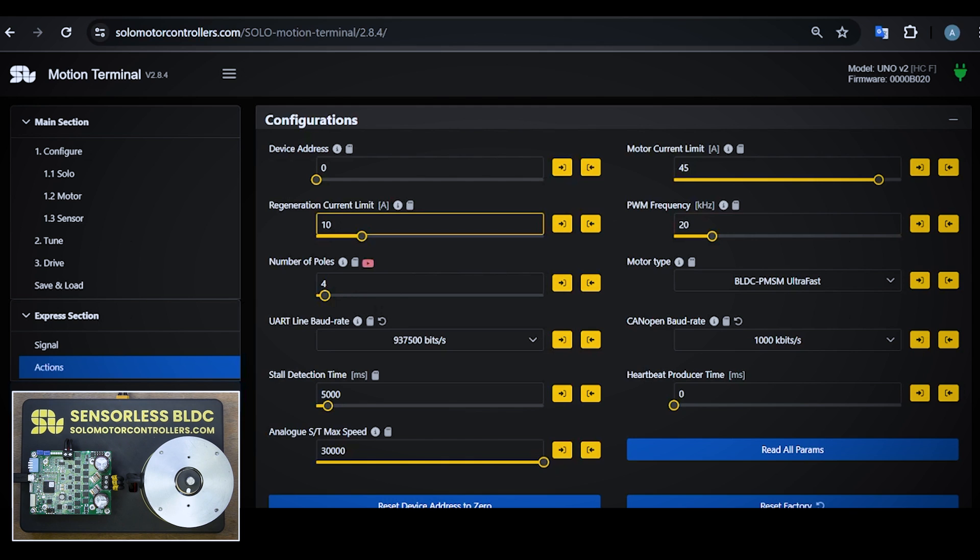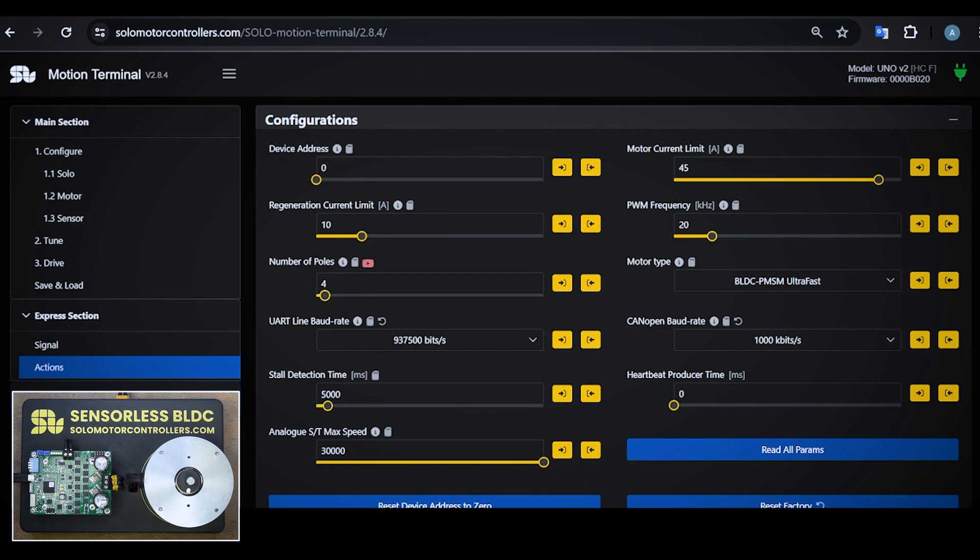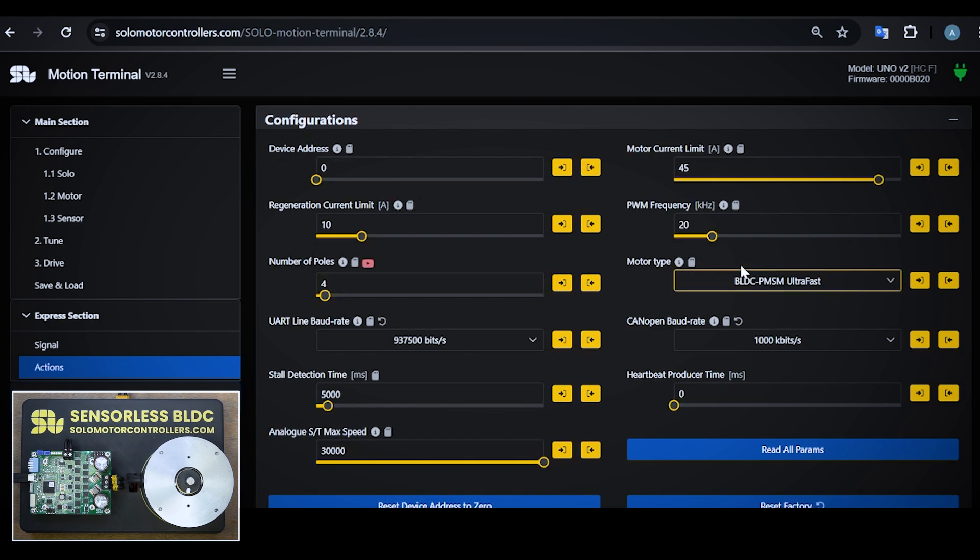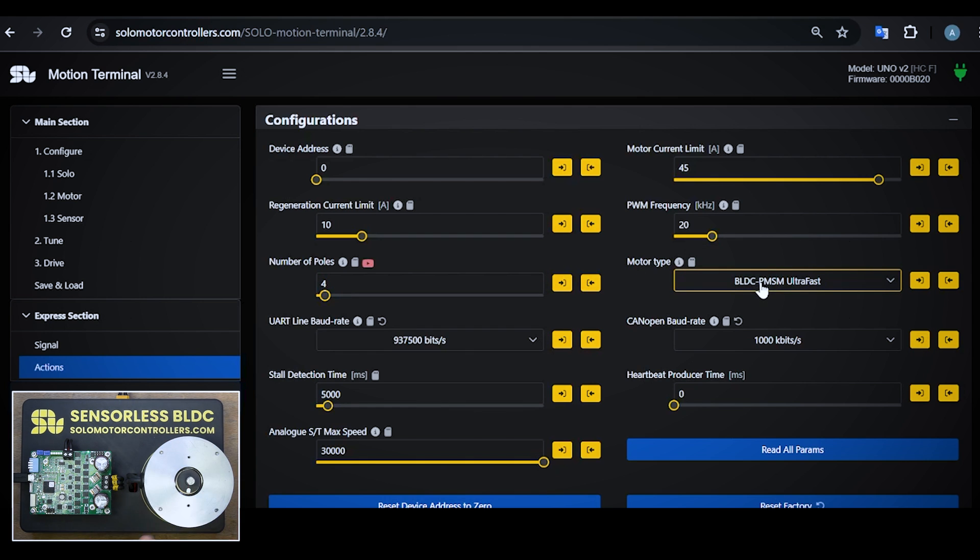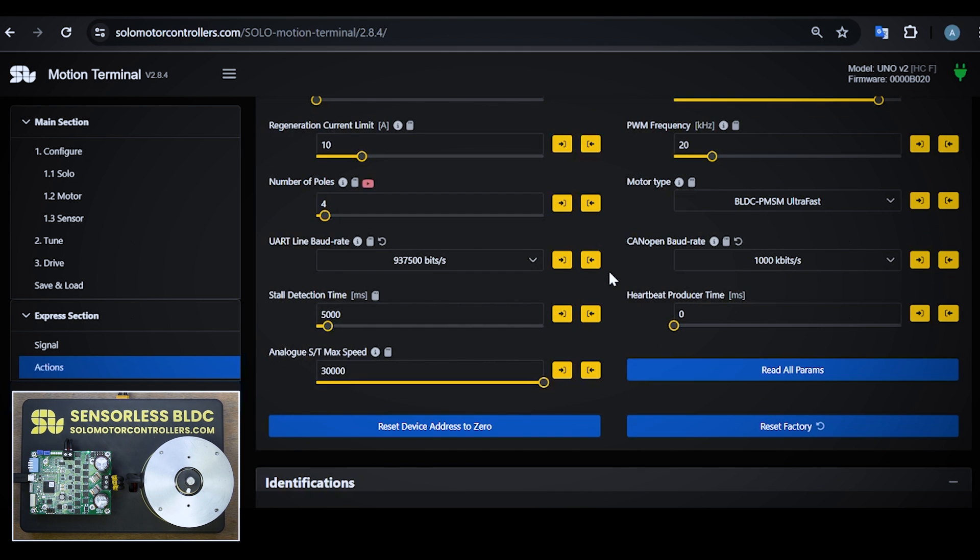Then you can set the regeneration current limit if you don't want to have current going back to your supply, but I recommend to keep a little bit of it here even if your supply cannot handle it, just to not reduce the dynamic performance of the system too much. Then we have the number of poles that should be selected correctly - here is four poles motor. And then finally we have the motor type that, as I'm reaching to very high speeds, I'm selecting BLDC PMSM ultra fast.